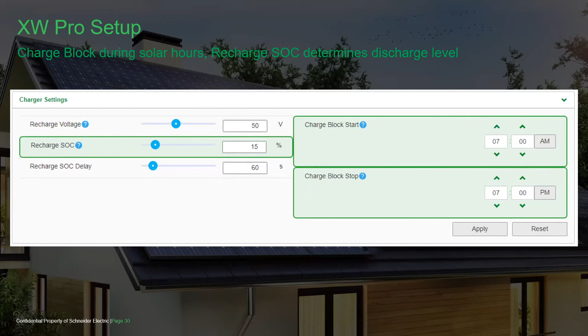And then, of course, the SOC control needs to be enabled. That's done in the battery settings menu. You can see that once you apply the BMS setup that we outlined in the previous slide, it'll automatically configure the battery type for lithium ion, and it'll automatically configure charge cycle for external BMS. So you don't have to do anything there, but you can disable or enable state of charge control, and we recommend for lithium that you enable state of charge control.